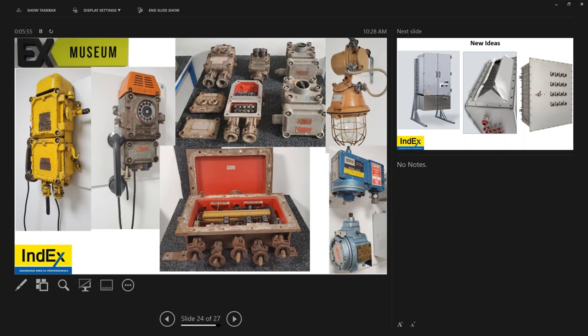But I've experienced it. In Canada, before on a class and division installation, we had empty enclosures. We drilled the boxes. We put the terminals inside of it. But it told us how many holes we were allowed to drill of NPT thread, with what type of drill press, and how to thread it, and how many terminals we were allowed putting into it. Is it dangerous? Yeah, I prefer the IECEx system fully.